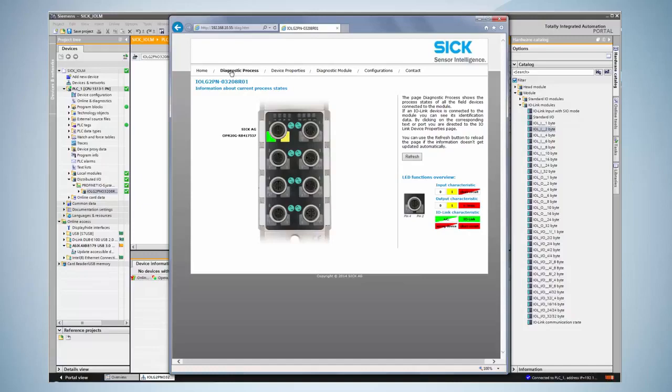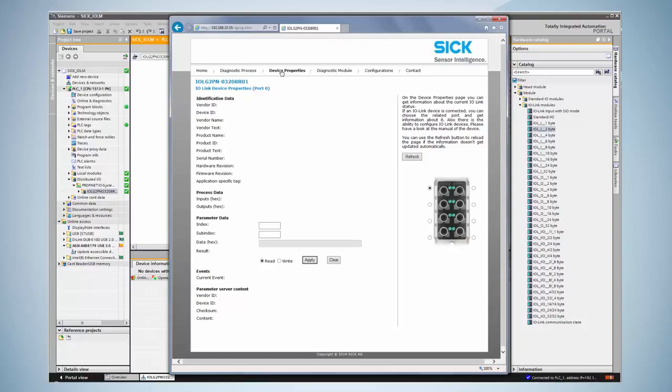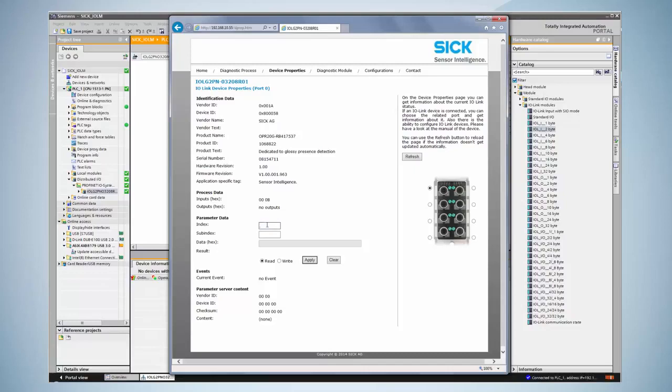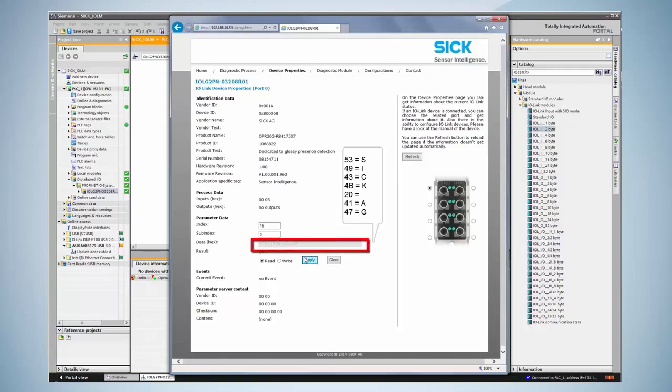By clicking on Device Properties service data of the IO-Link device can be read or written. As an example the standard index 16 is displayed. This index is the vendor name of the connected device. By reading index 16 the IO-Link master reads the data and visualizes it as an ASCII based hex stream. In this case the displayed name is SICK-AG.